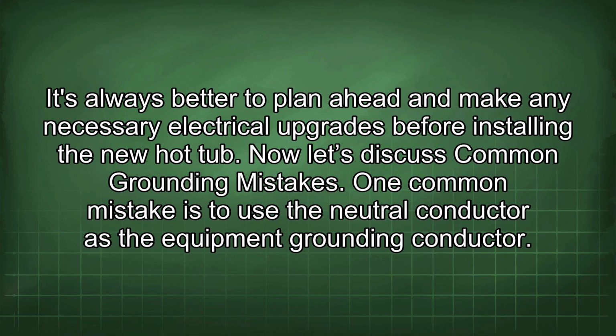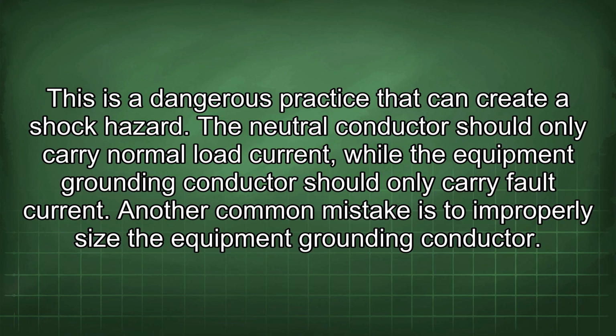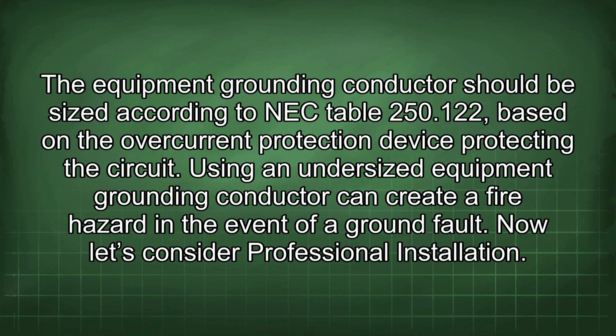Now let's discuss common grounding mistakes. One common mistake is to use the neutral conductor as the equipment grounding conductor. This is a dangerous practice that can create a shock hazard. The neutral conductor should only carry normal load current, while the equipment grounding conductor should only carry fault current. Another common mistake is to improperly size the equipment grounding conductor. The equipment grounding conductor should be sized according to NEC Table 250.122, based on the overcurrent protection device protecting the circuit. Using an undersized equipment grounding conductor can create a fire hazard in the event of a ground fault.